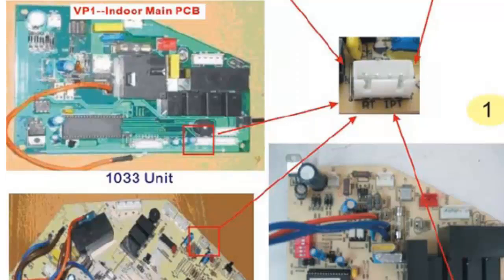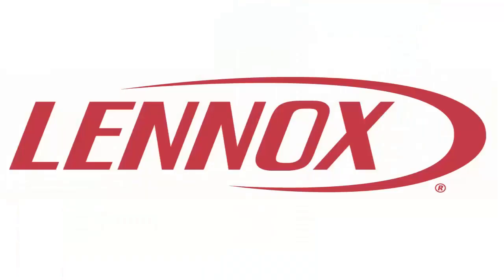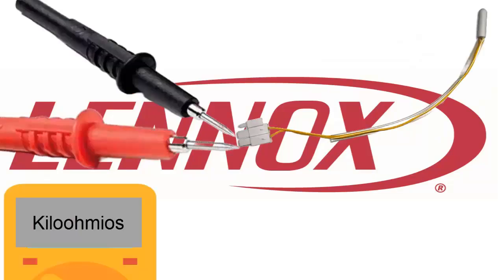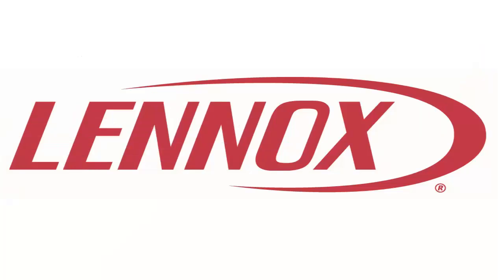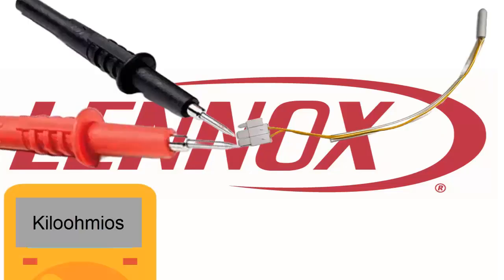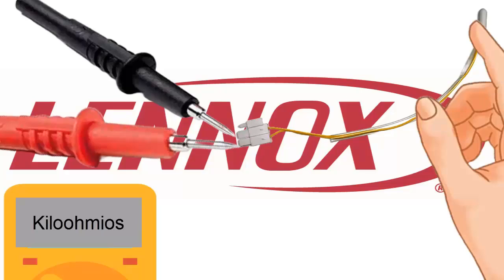6. If the error persists, turn off the unit, disconnect the sensor, and measure its electrical resistance with a multimeter in the kilo-ohm scale. The measured value should never be 0 or infinite. If it is, replace the sensor. Remember that when you rub the sensor with your hand, the resistance value should decrease. If it doesn't, replace the sensor.